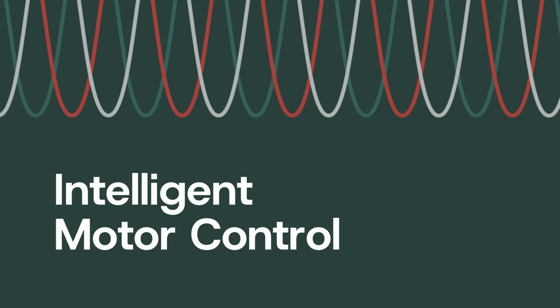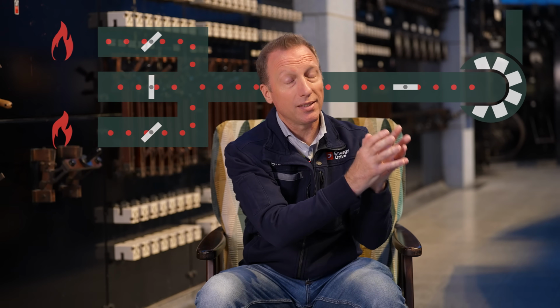When we talk about intelligent motor control, what we're really doing is understanding the process requirements, what the system really needs, and then satisfying those process requirements with as little electrical energy coming into the system as possible. If we take a fume extraction system, let's say, we often come across those with partially closed dampers. If we were to open those dampers, reduce the losses associated with the dampers, slow down the fan, we can satisfy the same process requirements, but with less power coming into the motor.